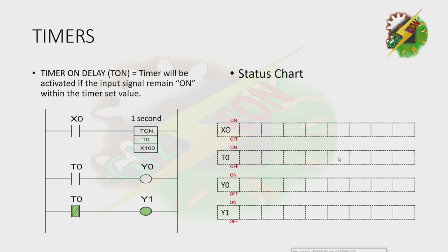Let's have our example. Initially, X0 is off, T0 is off, Y0 is off, and Y1 is on — because Y1 is connected to normally closed T0. On our timer, we have timer 0 and K100. K stands for constant, so we have a value of 100 multiplied by 10 milliseconds, which gives us 1000 milliseconds, or equivalent to 1 second.